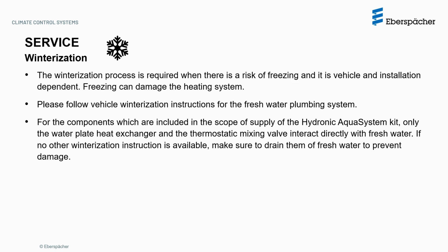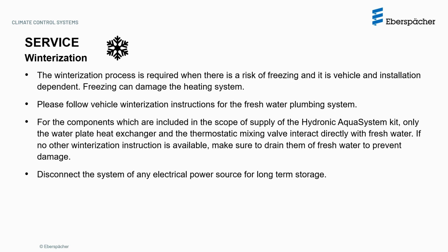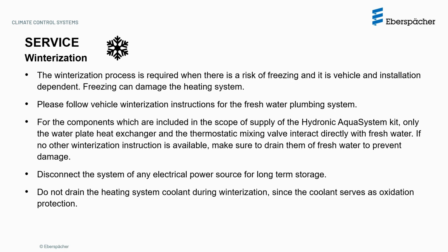For the components which are included in the scope of supply of the Hydronic Aqua System kit, only the water plate heat exchanger and the thermostatic mixing valve interact directly with fresh water. If no other winterization instruction is available, make sure to drain them of fresh water to prevent damage. Disconnect the system of any electrical power source for long-term storage. Do not drain the heating system coolant during winterization, since coolant serves as oxidation protection.